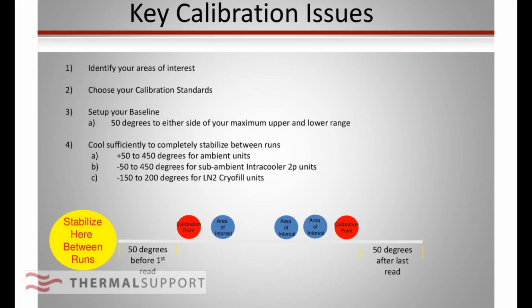You know, when we're going to calibrate, the most important thing is going to be that, number one, you have a solid baseline. Number two, to the best of your ability, you're going to want to bracket your sample with calibration points. DSC7 will only do two calibration points. But if you're running from 50 to 250, it's real simple. If you're running anywhere in the ambient region, it's a lot simpler than if you're going down to -50, going down to -150.